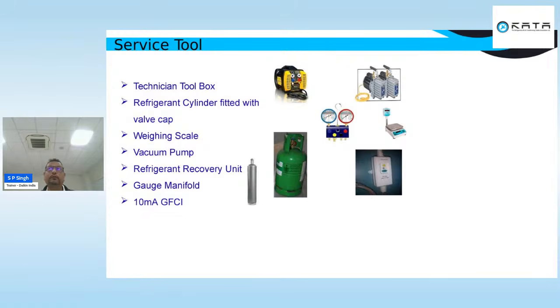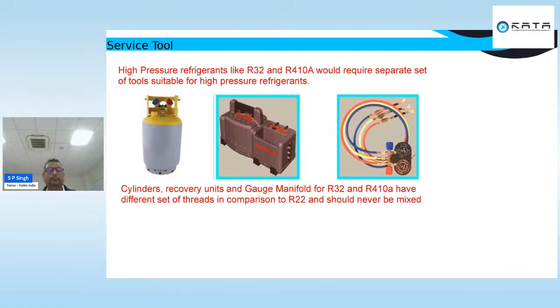Apart from that, a weighing scale should be there, a proper weighing scale, so we can charge the refrigerant in a proper way. Apart from that, a vacuum pump is required. Because R32 and 410 require some different manifold gauges, at least we should keep separate tools and charging pipes, because R22 is a mineral oil system, and R32 and 410 are synthetic. So the oil grading is different, and the viscosity is different. Based on that, a hazard can take place. So we should be very careful when we are charging the refrigerant, or when we are recovering the system.